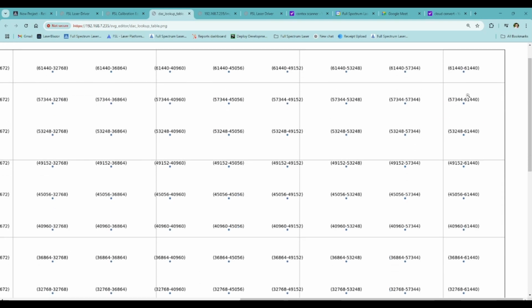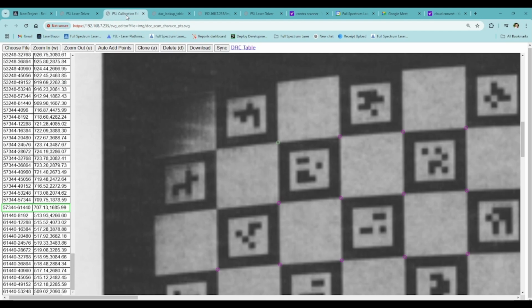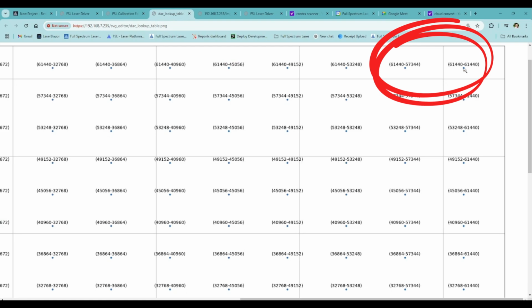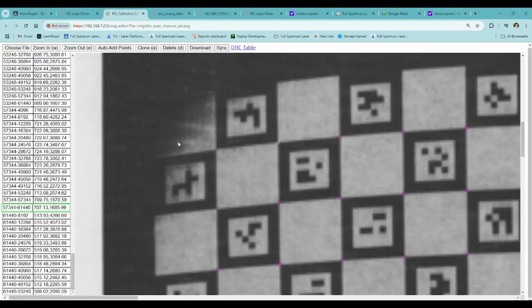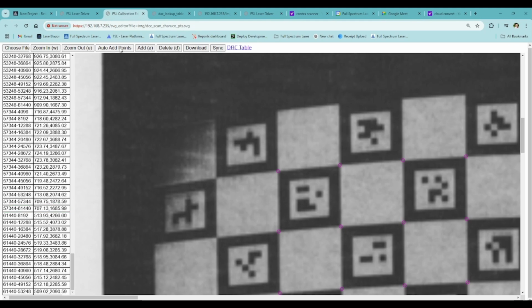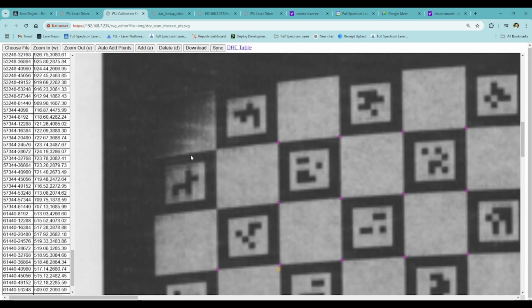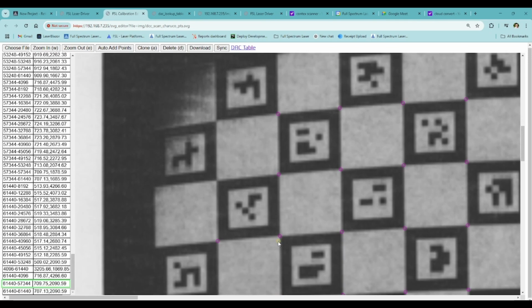I have located my reference point, which I am using to identify the missing dots. By analyzing the surrounding points, I can determine which ones need to be added. Since my scan is sideways, I have identified the 2 missing points located in the top left corner of my scan. We can select Auto Add Points, which will assign values to the missing dots. Then, we can locate the correct dots highlighted in yellow and move them to their corresponding positions. I will continue this process for my other 2 missing points.